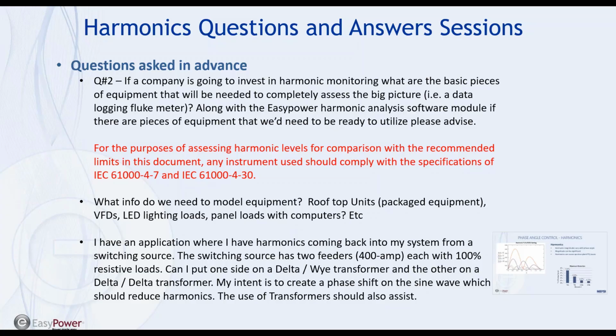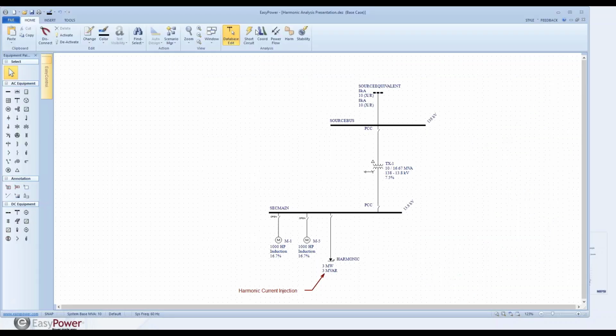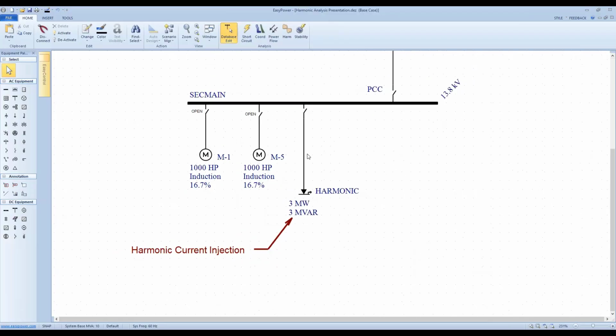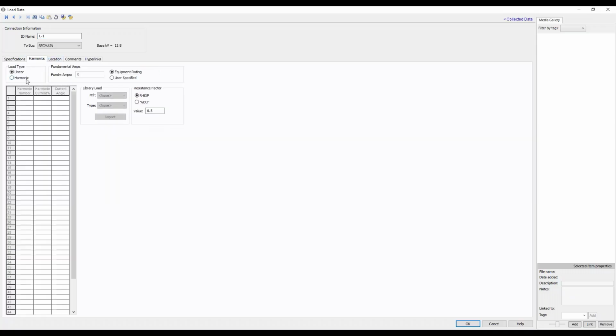Okay, so next question. What do we need to model equipment, rooftop units, package equipment, VFDs, LED lighting loads, panel loads with computers, etc.? So this is a modeling question. When you model harmonic load, and I guess I would jump over to EasyPower real quick. When you model harmonic load in EasyPower, what I've done is I put a load on the bus here. That's simply done by grabbing the load over here and double clicking the load. And the harmonics tab shows the input requirement, and if you have a harmonic, you click the harmonic button there, and from there you have to put in some values. The tab itself is looking for harmonic number and harmonic current percent here, and you're actually modeling the harmonic current injection that device puts out.